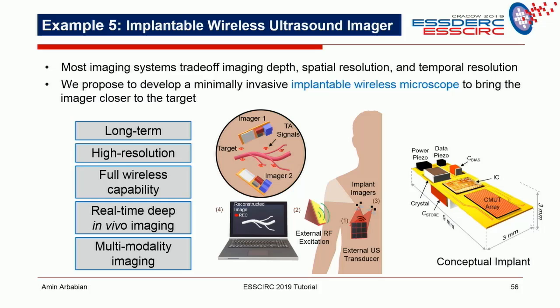Now, on the chip, we have an ultrasonic receiver array that's measuring the response from this pulse, but it's powered and controlled completely by the external device that's a wearable. So the wearable device sends power and data, or receives the data from the implantable imagers that are sitting around tissue, and this CMUT array, or ultrasonic CMUT array, receives the data, averages it on chip, because we don't have a gigabit per second data link, and about 1 to 2 frames per second sends the data out. Right? So that's the whole purpose of this. It's designed to be long-term usage, high resolution, fully wireless, give you in vivo capability, and it's a multi-modality imaging system. It uses RF or optical together with acoustics.